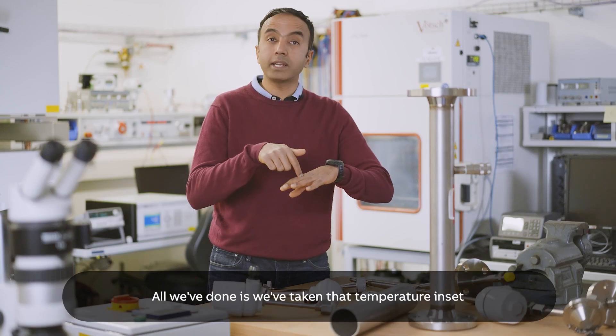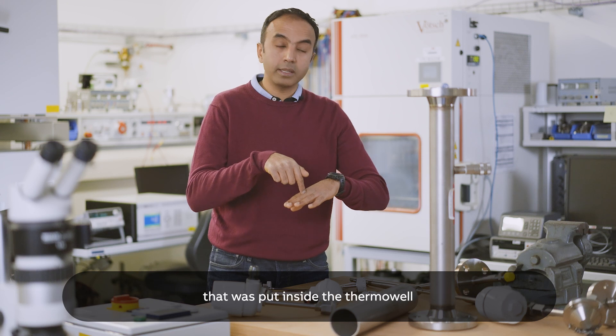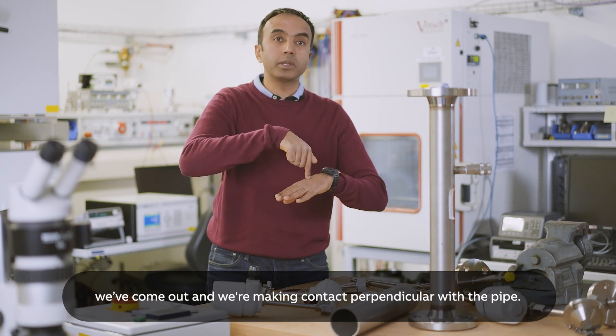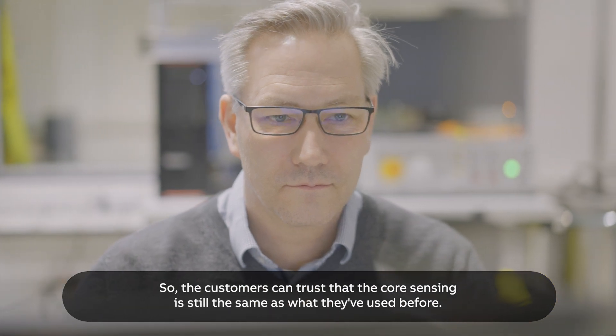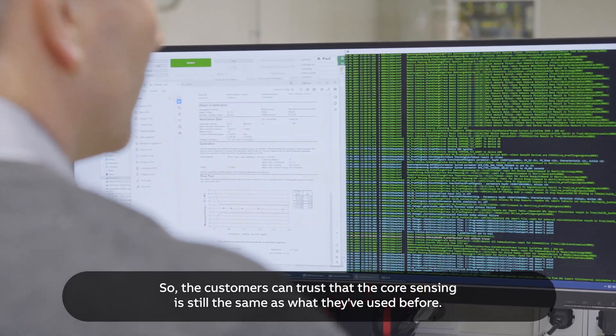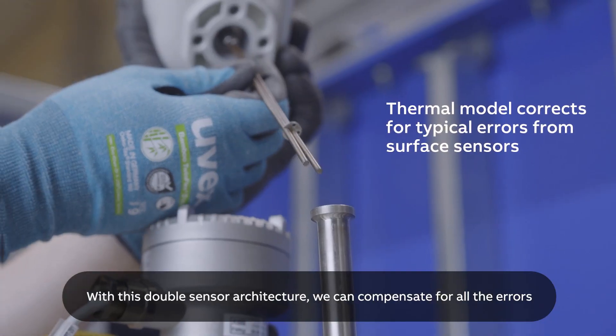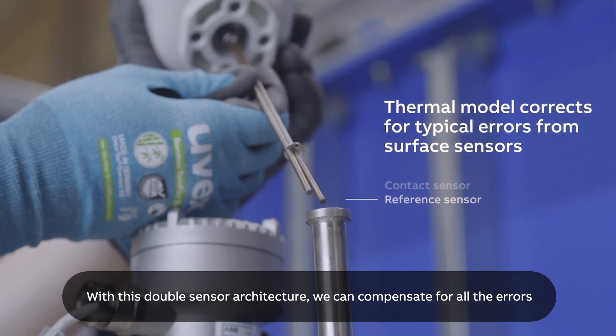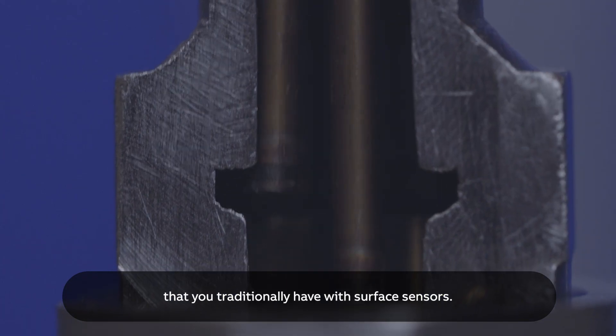All we've done is we've taken that temperature insert that was put inside the thermowell, we've come out, and we're making contact perpendicular with the pipe so the customers can trust that the core sensing is still the same as what they've used before. With this double sensor architecture, we can compensate all the errors that you traditionally have with surface sensors.